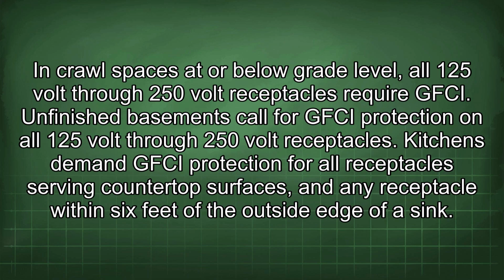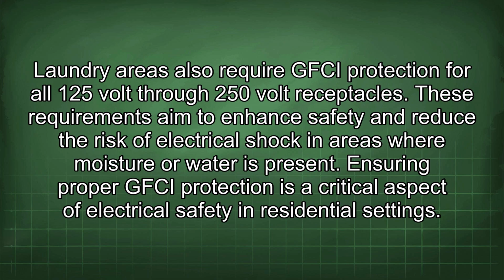In crawl spaces at or below grade level, all 125 volt through 250 volt receptacles require GFCI. Unfinished basements call for GFCI protection on all 125 volt through 250 volt receptacles. Kitchens demand GFCI protection for all receptacles serving countertop surfaces and any receptacle within 6 feet of the outside edge of a sink. Laundry areas also require GFCI protection for all 125 volt through 250 volt receptacles. These requirements aim to enhance safety and reduce the risk of electrical shock in areas where moisture or water is present. Ensuring proper GFCI protection is a critical aspect of electrical safety in residential settings.